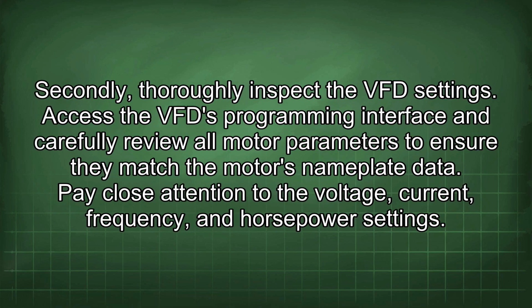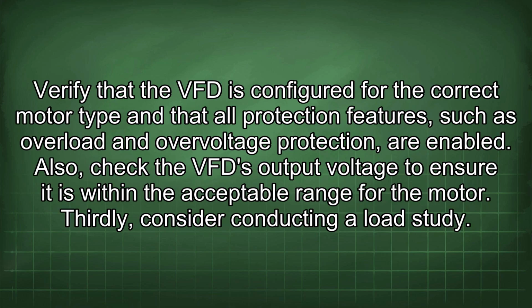Secondly, thoroughly inspect the VFD settings. Access the VFD programming interface and carefully review all motor parameters to ensure they match the motor's nameplate data. Pay close attention to the voltage, current, frequency, and horsepower settings. Verify that the VFD is configured for the correct motor type and that all protection features, such as overload and overvoltage protection, are enabled. Also check the VFD output voltage to ensure it is within the acceptable range for the motor. Thirdly, consider conducting a load study.